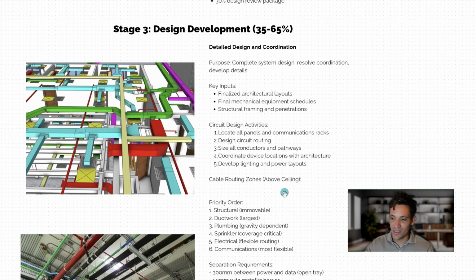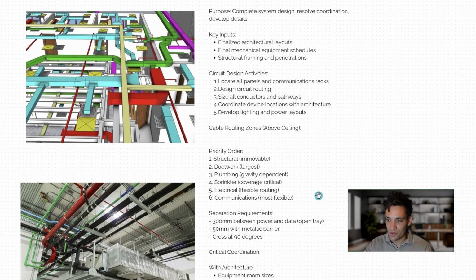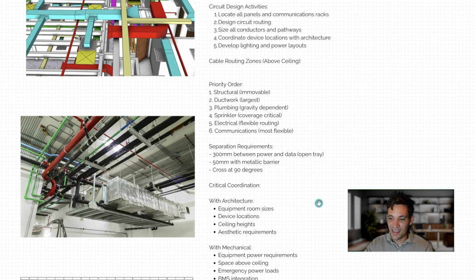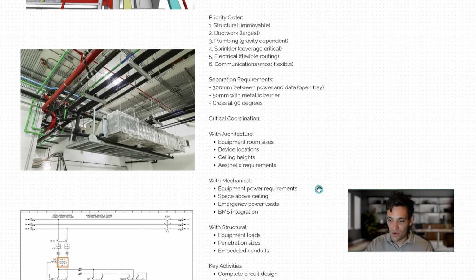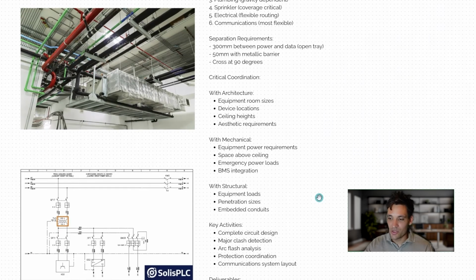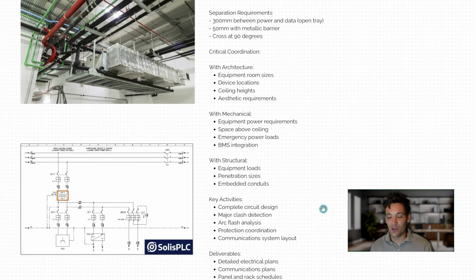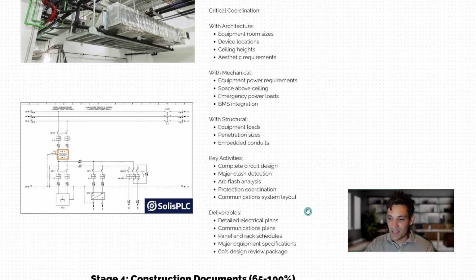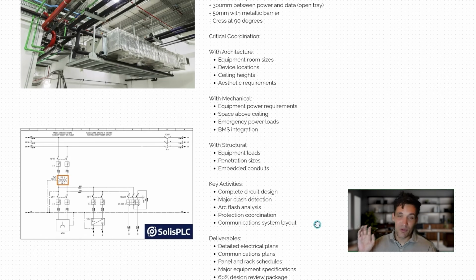We can start sizing all our cables, creating a detailed cable schedule, finalizing all our equipment, starting to consult with our vendors to confirm what specific vendors and products we're using, and space proofing those products. Because again, we might specify a main switchboard in an initial layout, but when we actually go talk to a vendor, they'll have slightly different layouts. We start integrating all that, to get it to a stage where we know where every load is going to be, how big every load is, where all the cables are running, what the size of those key cables are, which key vendors we should choose at this stage, and where all the penetrations are going to be.